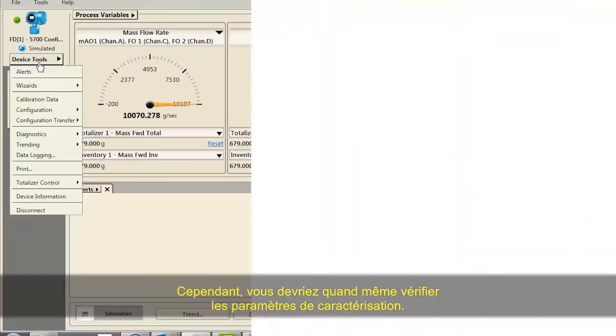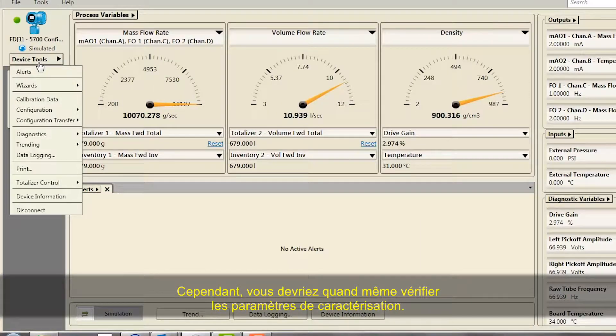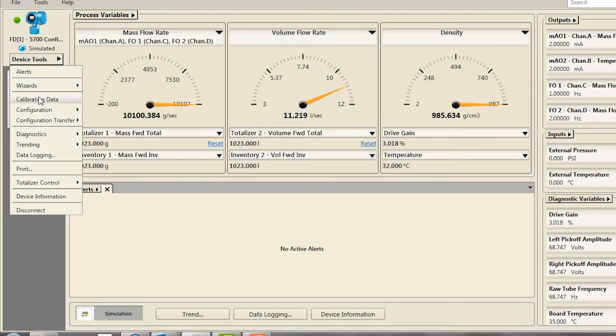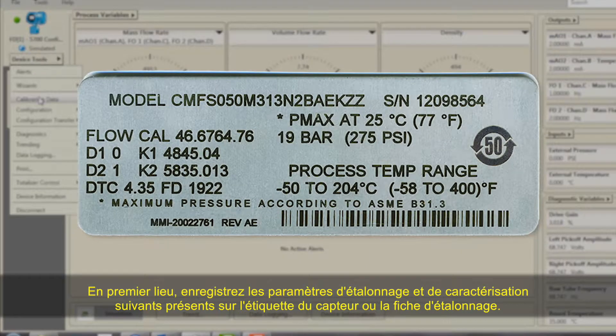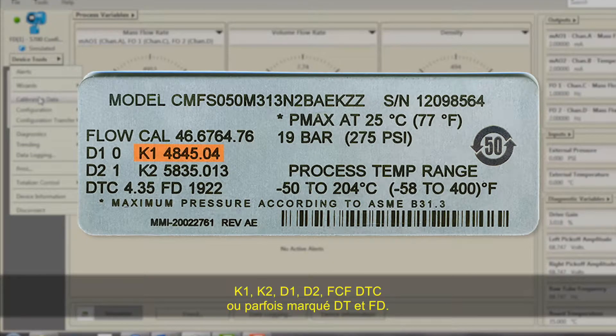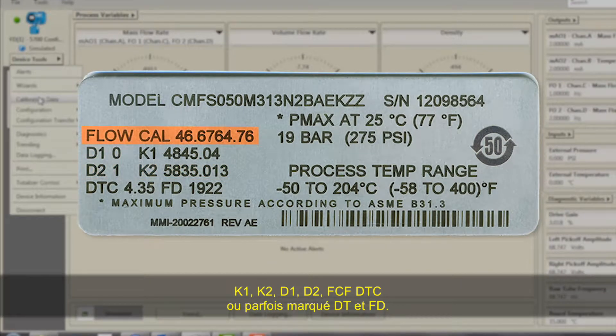However, you should still verify the characterization parameters. First, record the following calibration and characterization parameters from the sensor tag or calibration sheet: K1, K2, D1, D2, FCF, DTC (sometimes labeled as DT), and FD.